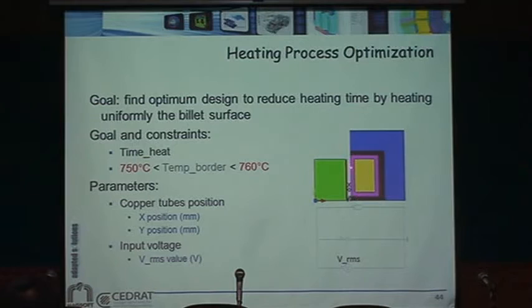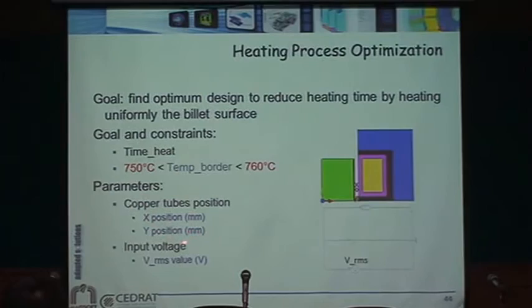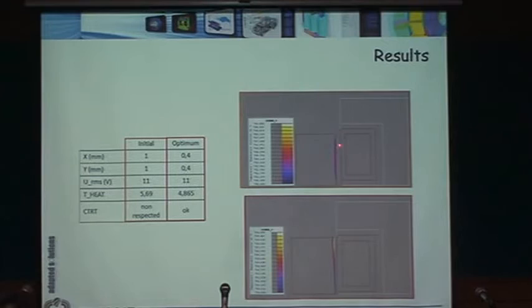Heating process optimization: we want to shape the induction coil so the surface temperature of the load is uniformly between 750°C and 760°C, while limiting the heating time. The initial coil only heated a small region. The optimized coil was moved slightly lower with a reduced air gap, giving a much more uniform temperature distribution across the surface.